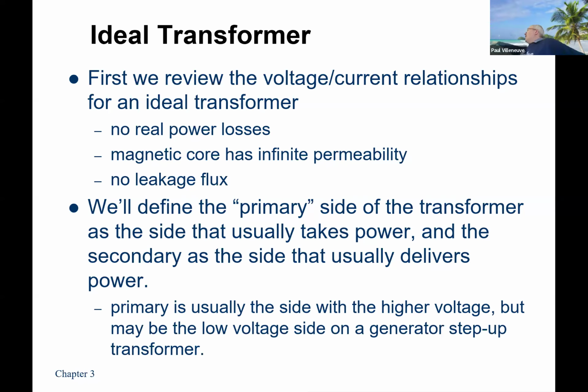The primary side is usually the one that takes the power, and the secondary side is the one that usually delivers the power. Normally, when you say primary side, you say high voltage side, right? Because like at our house or even in this building, the high voltage comes in at 4160, and then it steps it down on the secondary side to 208. But that's not always the case. Think of a generator step-up transformer. The generator generates at like 22,000 volts and immediately takes that voltage and steps it up to maybe 345 kV and sends the power to the grid. So primary is the side the power goes in, and secondary is the side that it comes out of, all right?